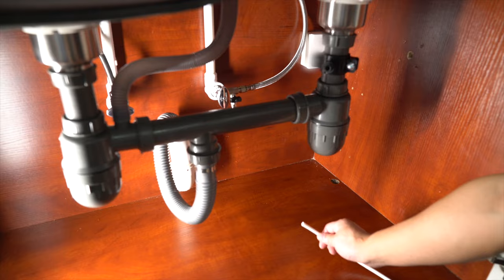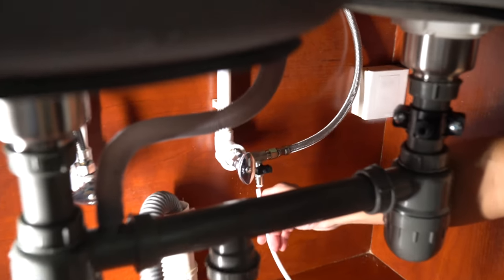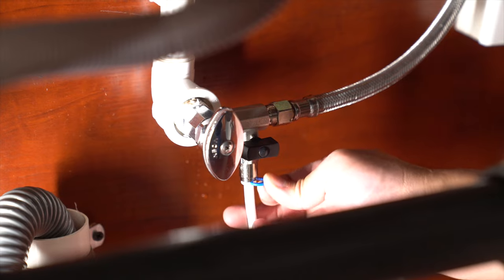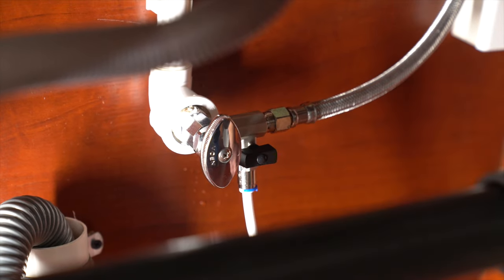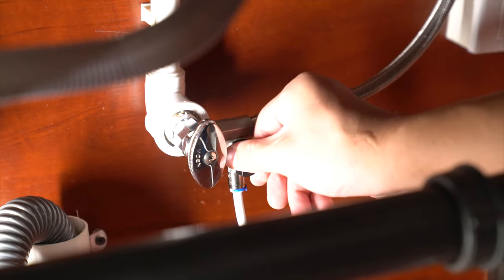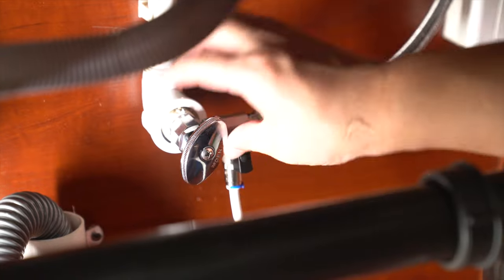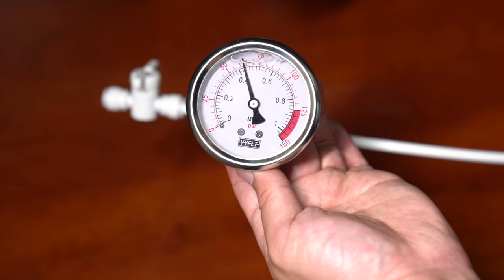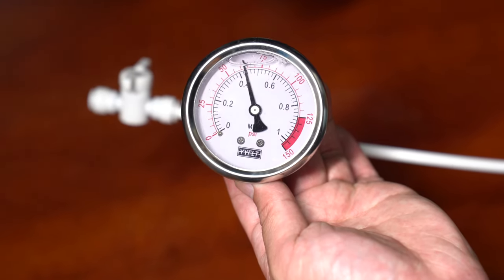Cold Water Pressure Check. Before you begin installation, confirm your cold water pressure is between 40 to 80 PSI using a pressure gauge. If lower than 40 PSI, a booster pump may be required. If over 80 PSI, a pressure reducing valve is required.